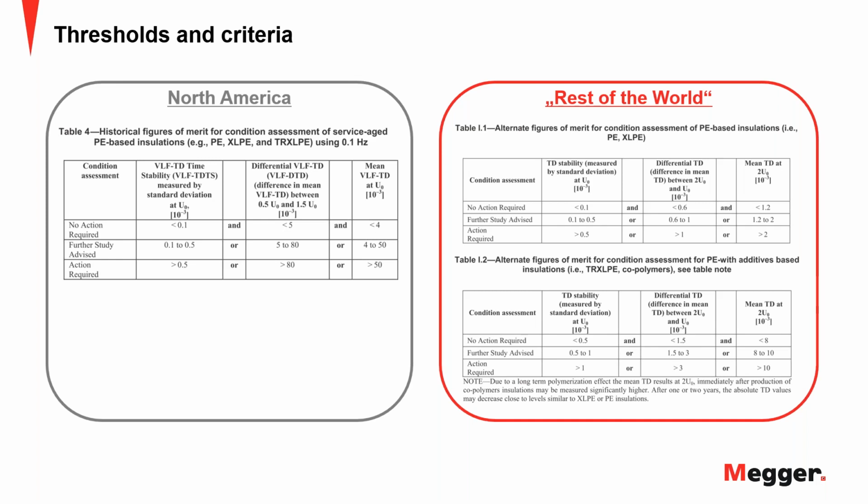So we know by experience that we have this and this and this in the circuits. So we have to pay attention to that and that and that. And this is why assessment based just on measurement numbers, on values, is one-dimensional. It's not good enough. You need to take into account all these other things, maybe even circuit history. If a circuit is notoriously known for failing, then you probably take a different approach to this circuit than to another circuit that might be electrically identical.